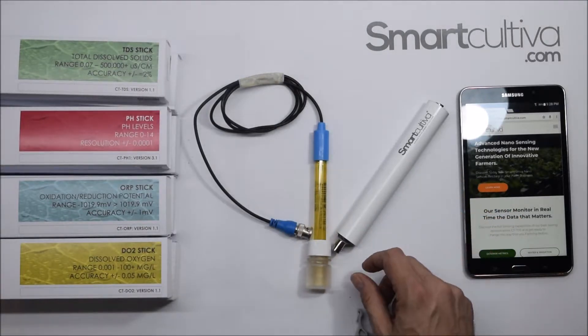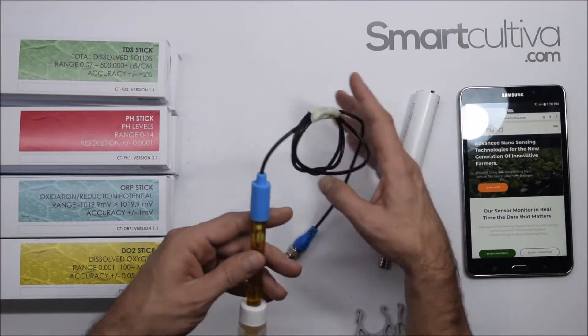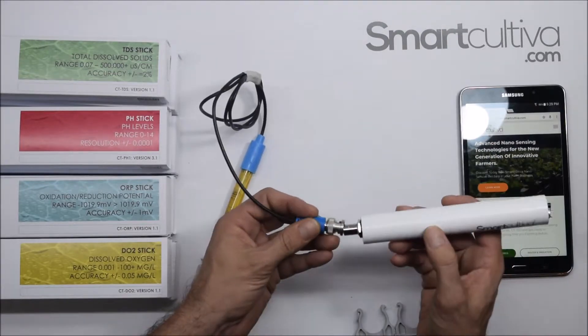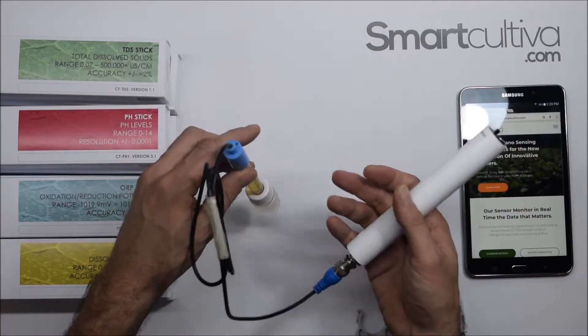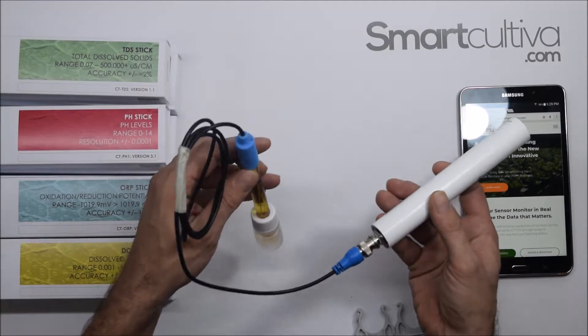Let's review the different connectors. In this particular case, we will use the pH probe — we simply connect the BNC connector here, and the probe is connected. All these probes that we'll be using are fully submersible in water.